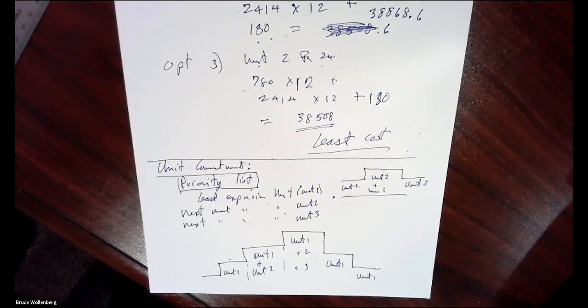If you're running online and you want to get the minimum, you want to squeeze as much economics out of the generators as you can, okay, then in daily use, you're going to use a really good unit commitment program and let it run for, it'll take time and be expensive to get all the data ready every time for it. But the priority list is easy. It's just dirt simple. You keep adding units until you got enough generation, and you do that every hour. That's it. That's priority list. It's very simple. Okay.